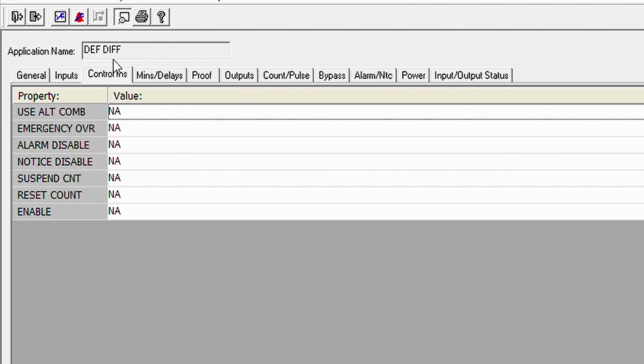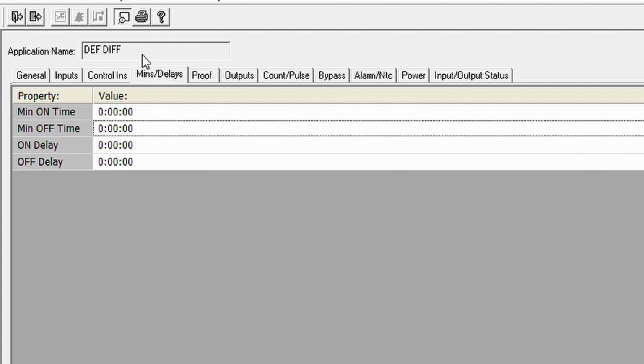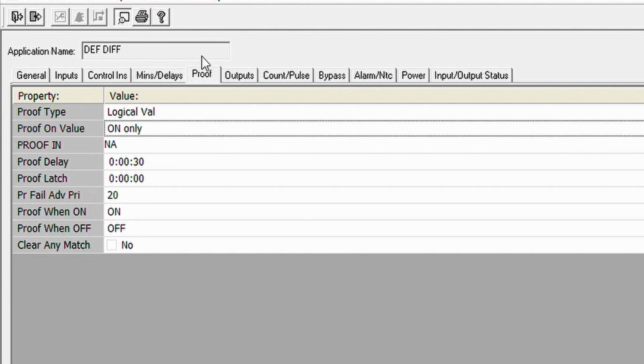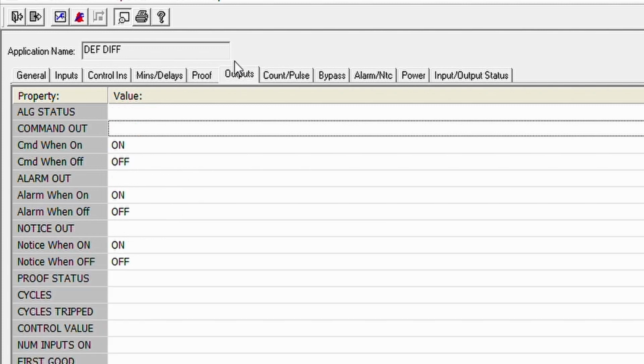So you get your controls in: your reset count, your alarm disable, your use alternative combination, your emergency override, your delays tab, your proofs tab. Same thing, you have your proof set up in here, your output. So your board point's going to go, or whatever it's controlling is going to go. So you can control multiple things off here.